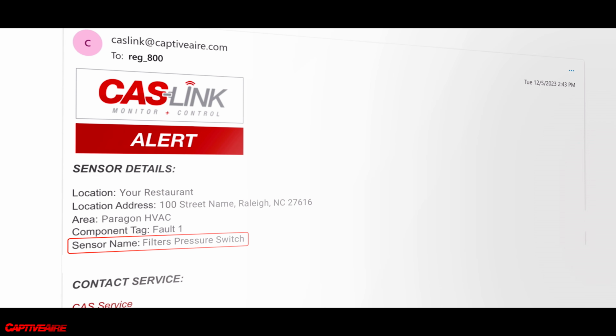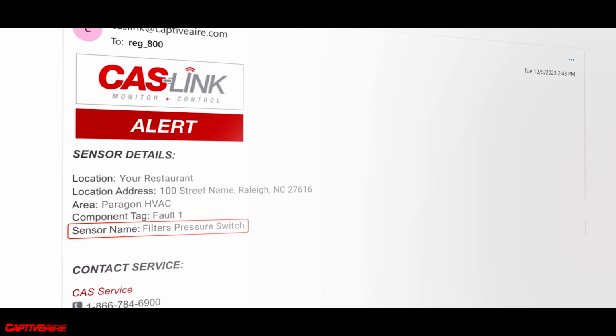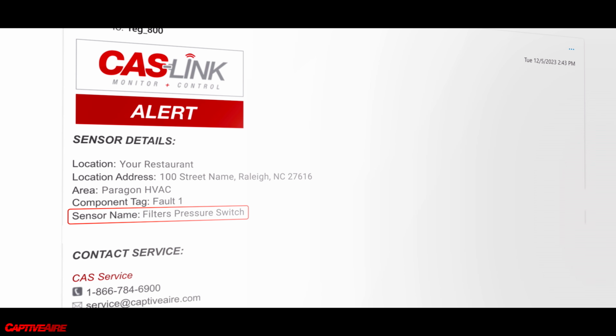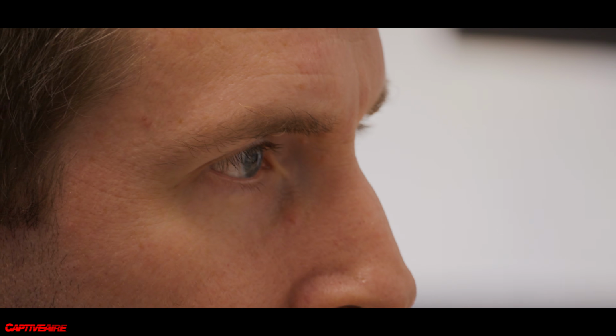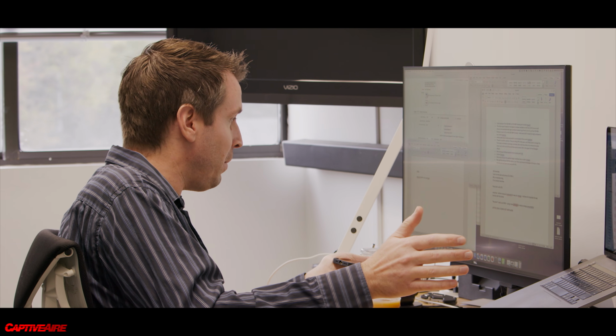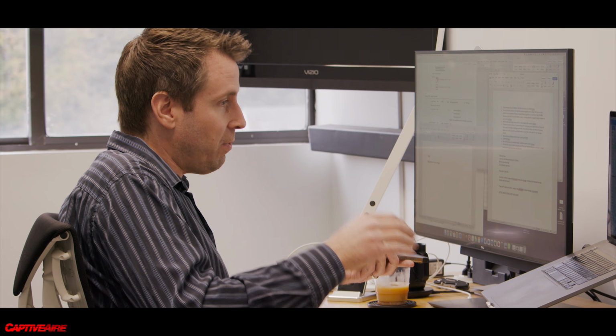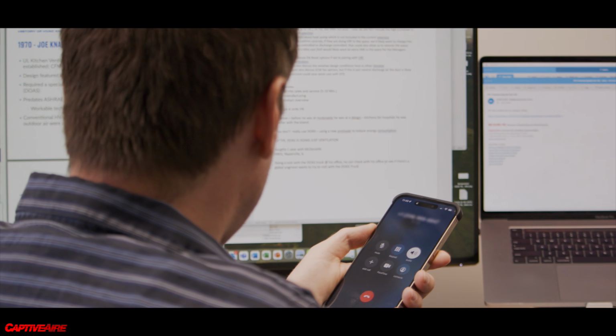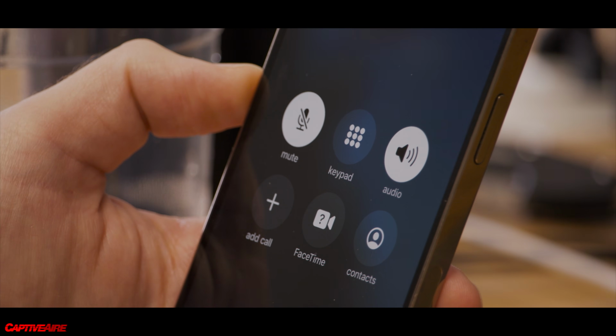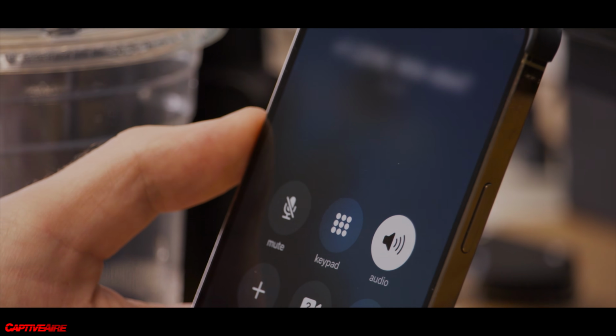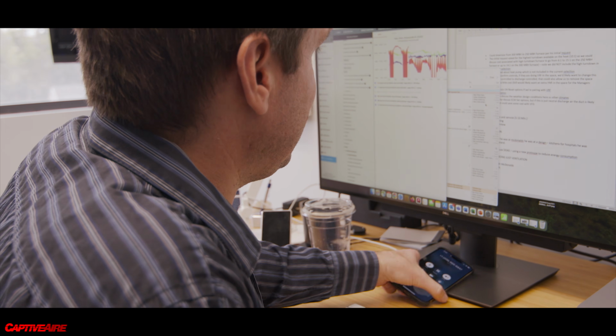You can set up these email alerts to any third-party service you want. At the very least, our own sales team and our own support teams will always be outfitted with those email alerts automatically for any system that's sold and set up. So that way, we make sure that on every single job site, if there's an issue, at least somebody's getting that email alert. And if it's a critical issue, we can get proactive and start reaching out to that customer. Oftentimes, we'll reach out to try and set up that site visit before the customer even realized that the unit had a fault. The name of the game here really is being proactive.